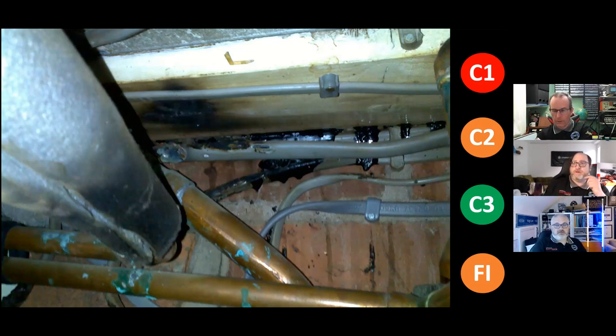I think, to me, as a minimum, it's a C2 with an FI to verify the integrity of the circuit. Again, I'm just curious. This is based on me sticking my head under a floorboard and seeing that visually. The cable is damaged. I can't see exposed copper from what I can see. The circuit may have had its integrity impeded, which is fine. Well, it isn't fine. So I need to do further investigation, without a doubt.